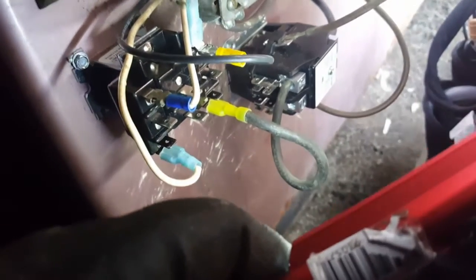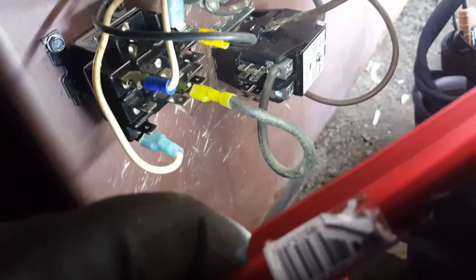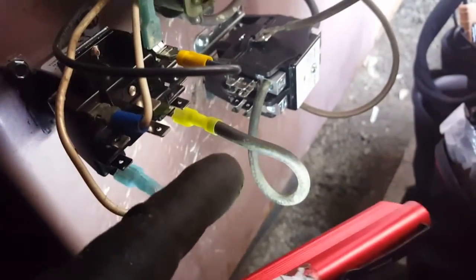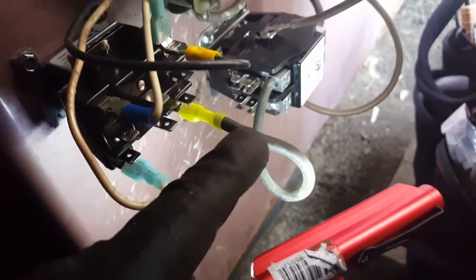So what we have here is two low voltage wires coming into either side of the contactor. It's a 24 volt coil on this contactor, and that's our G and common. Then we have a 120 volt power leg coming into this contactor, passing through, powering up the coil here. This is a 120 volt coil on this double pole double throw relay. You can see it's protected down there at the bottom. So, a 120 volt coil there.